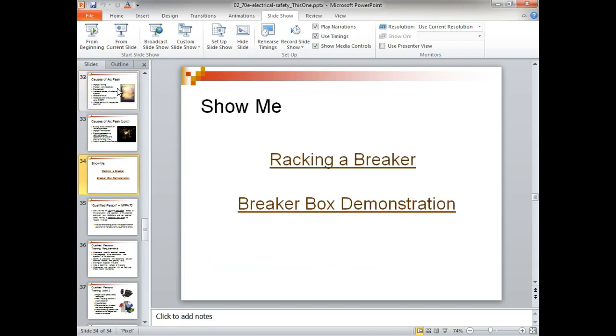The breakers they have in industry are so big. What they do is called racking a breaker. When you install a breaker, you rack it - basically it's a big square with all the stuff in there that gives you the breaker. You set it on a set of rails, and then you wind it in, and as the carriage gets up in the back, it actually inserts itself into the high voltage, high current.